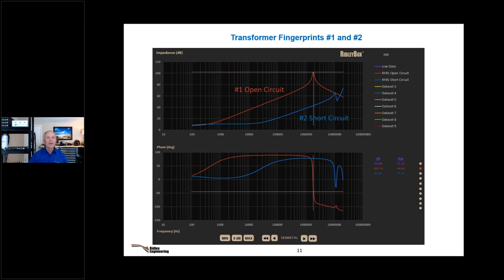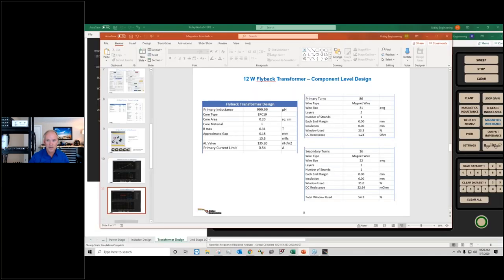So what we've done here is taken a little fingerprint of our transformer, which is that open circuit measurement. That's the first thing that we do. And I know many of you do this kind of unofficially, or you've learned this, or low frequency motors often get these sweeps done on them. The next thing we want to do is the short circuit measurement on our transformer. So let's go ahead and do that.